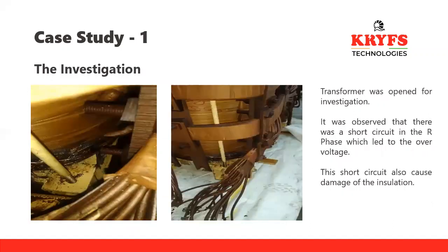So the end customer, Vision Industries, sent this transformer to a transformer factory to rectify the problem caused by the increase in voltage. There was some damage in the transformer. What we investigated was that on the R phase there was a flashover, because of which the windings got shorted, and it had already damaged the insulation property of the winding.